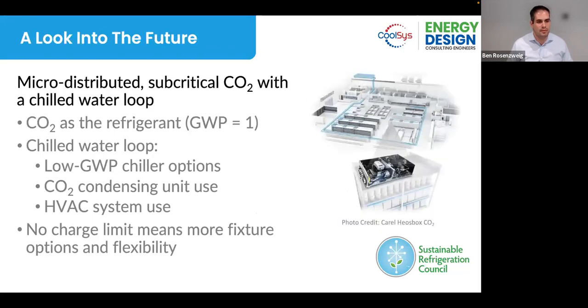Next slide, please. So just briefly, while I wrap up here, a look into the future is something like this, where you can have a system based on subcritical CO2 as the refrigerant cycle, where it's a truly micro-distributed system using a water loop, where you're using CO2 with the reference GWP of 1 as your refrigerant, even lower than propane or some other options. And you'd be able to place these units throughout the store. You'd have a water loop, albeit it would need to be using a chiller to get the temperature low enough. And that chiller should be specified with low GWP as a refrigerant in order to continue down the path of designing low GWP stores and not increasing the amount of GWP that your store might have.